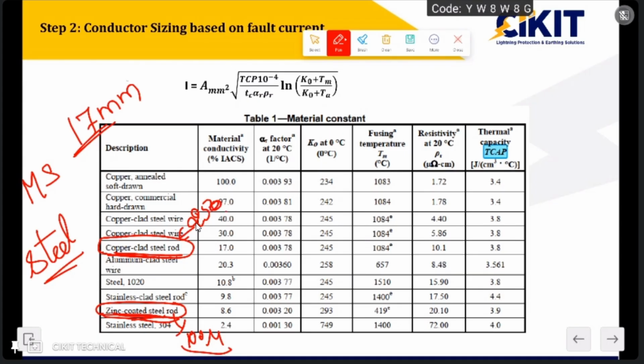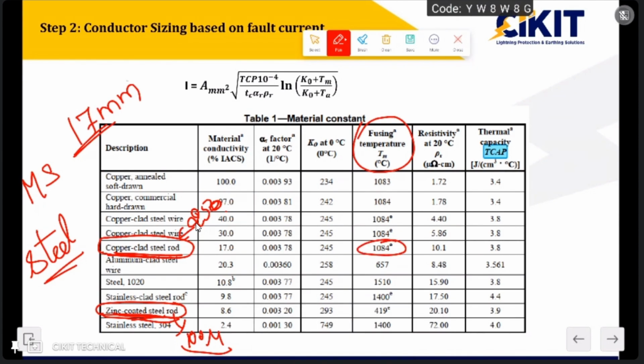Even though the difference is mainly because of this microns, there will be a huge difference in the current carrying capacity. And the reason behind this huge difference is the fusing temperature. So for copper, the fusing temperature is 1084 degrees centigrade, whereas for zinc it is only 419 degrees centigrade.